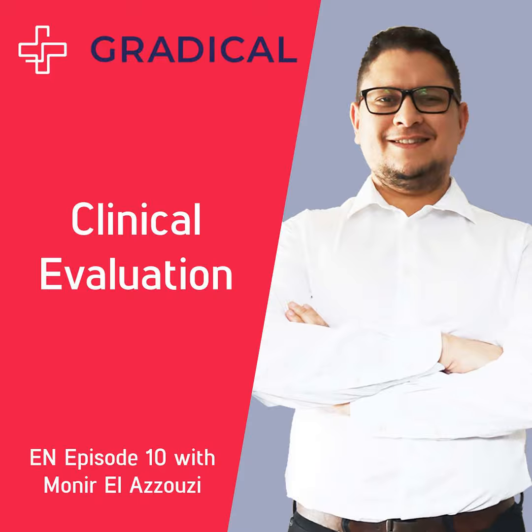The third one is clinical. Mainly, the product should be clinically used for the same purpose, the same disease, the same stage of the problem, the same population, and so on. So these are the three: technical, biological, and clinical. If you can prove that all those three aspects are covered, there are similarities. As I've said, there can be some differences, but you have to justify that those differences are not significant. If you cannot justify that, then you cannot claim that this is equivalent.